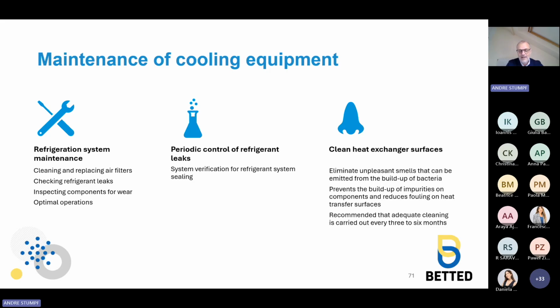So we speak about the evaporators and the condensers. The appropriate cleaning process can eliminate unpleasant smells that can be emitted from the buildup of bacteria in the system. It also prevents the buildup of impurities on components and reduces fouling on heat transfer surfaces, ensuring clean heat exchanger surfaces for efficient performance. It is recommended that adequate cleaning is carried out every 3 or 6 months as part of a regular service and maintenance program. Frequent cleaning of a system increases reliability and efficiency, means fewer failures, and provides long-term protection and peace of mind for users.